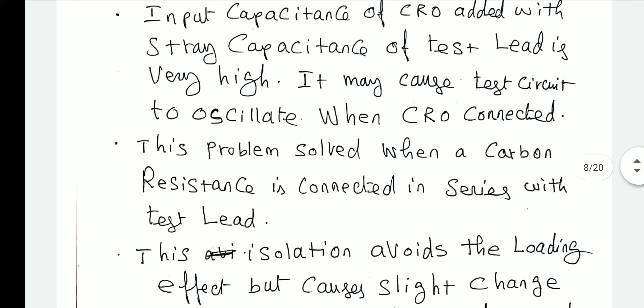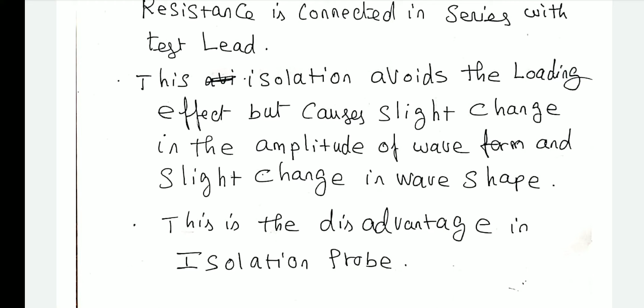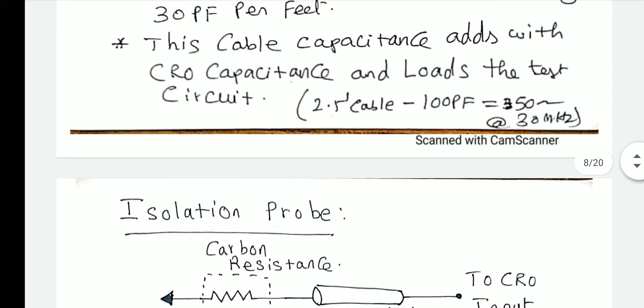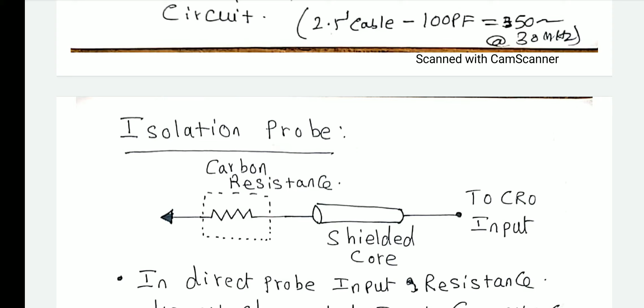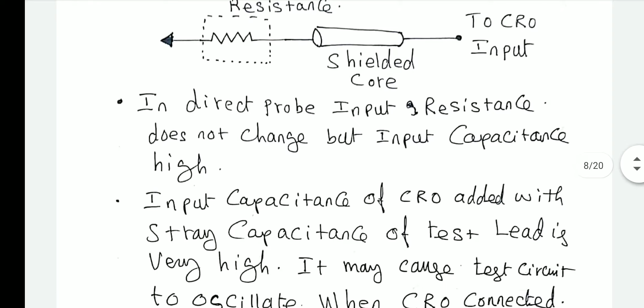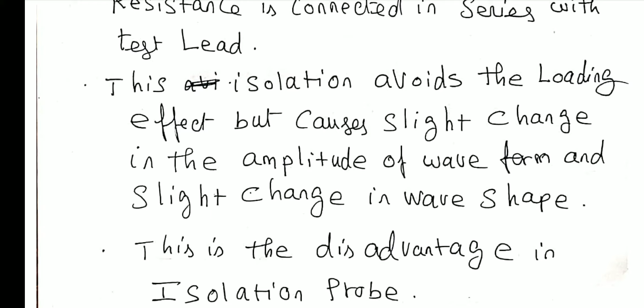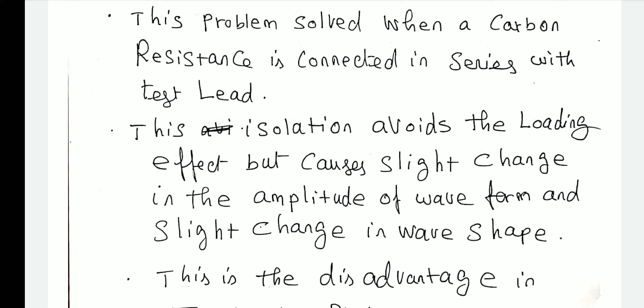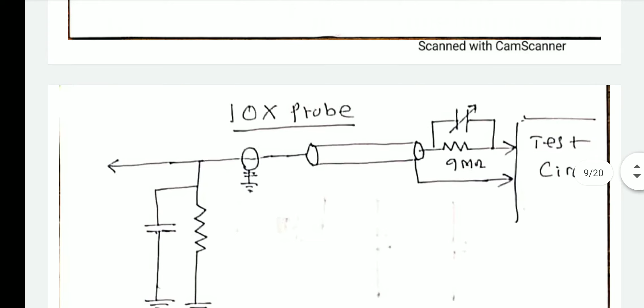Now this is the advantage of the isolation probe, but there is a disadvantage. Whenever there is a slight change in the amplitude of the waveform and wave shape, it happens because of this resistance - we are connecting a resistance in the signal path. So when the signal flows through this, the magnitude of the signal decreases. Hence there is a slight decrease in the amplitude, and the waveform shape also changes. That is the disadvantage in the isolation probe. So the advantage is it isolates the capacitance, but the disadvantage is that because of the resistance, it reduces the amplitude of the signal. That is the problem - the amplitude should not be affected.